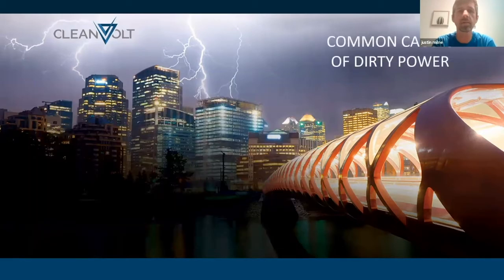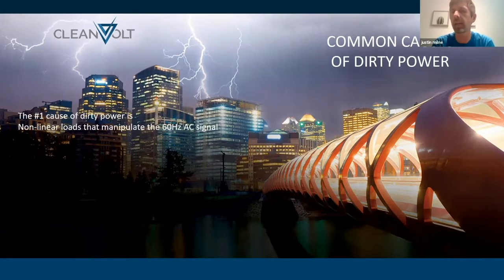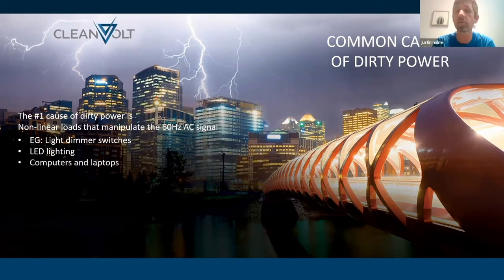So common causes of dirty power are, of course, electronics that manipulate the 60 hertz signal or nonlinear loads. Light dimmer switches are known to manipulate the voltage up to 1,000 times per second in order to get the dimming effect that you're requesting. LED lighting is electronic in nature. Computers and laptops, printers and scanners, TVs, VFDs are notorious for creating line noise.